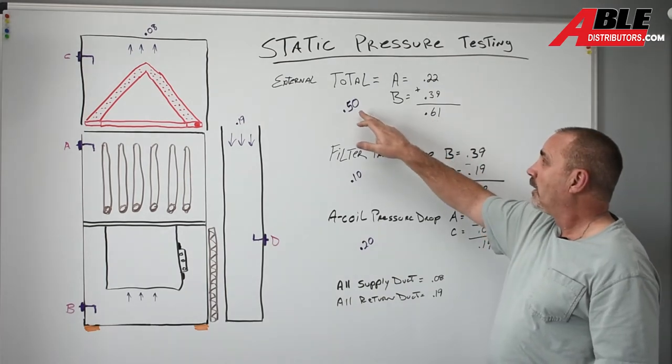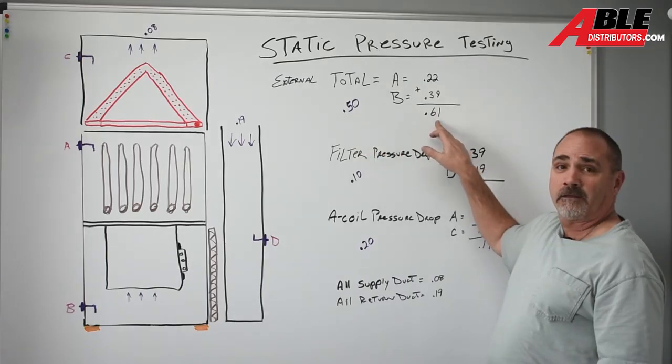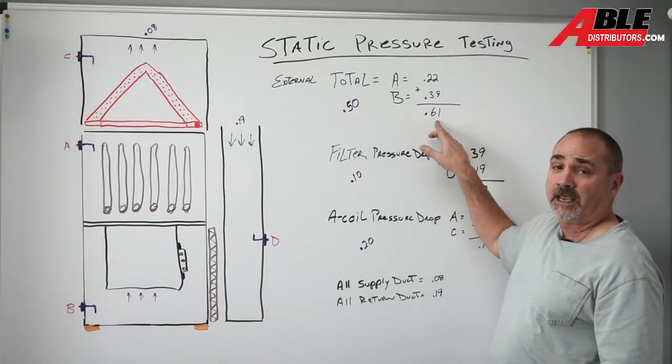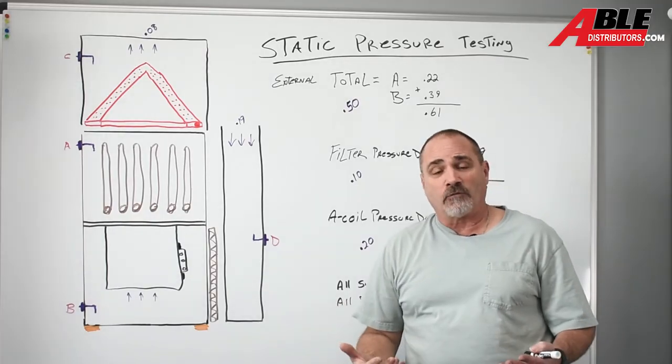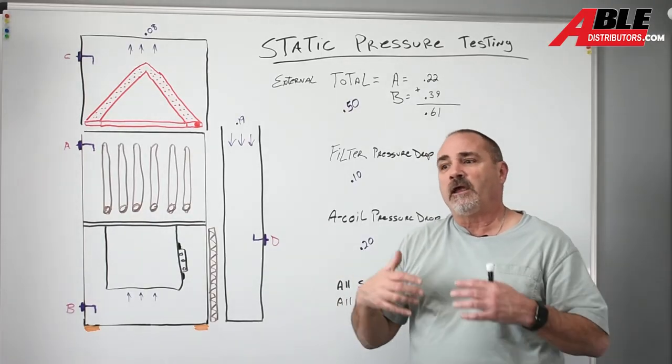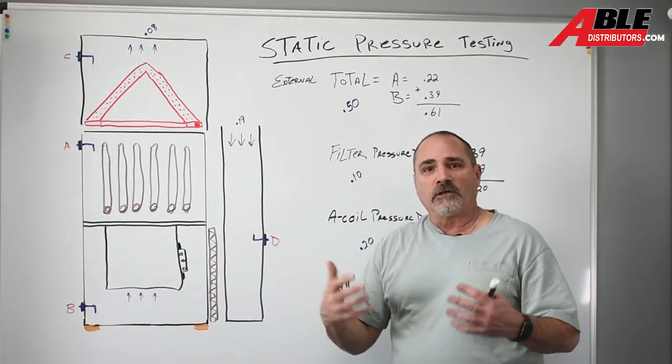The difference between a 0.50 and 0.8 might be 200 CFM, that's half a ton. It might be seven degrees temperature rise. So you can see how the airflow and that static starts to affect it.